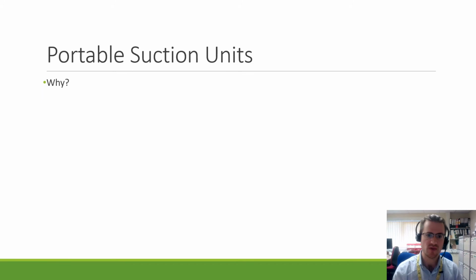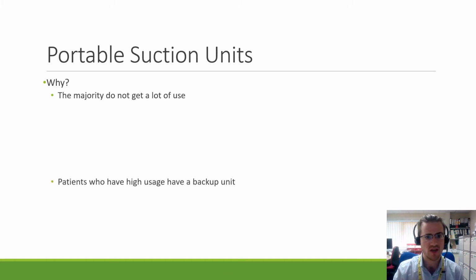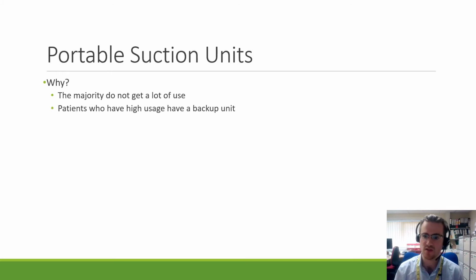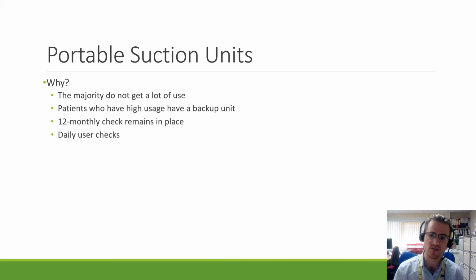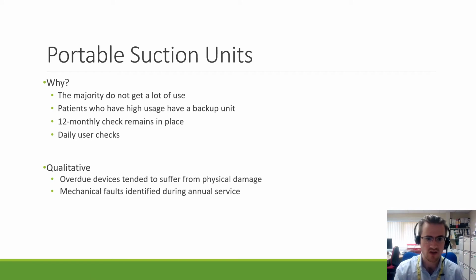For portable suction units, why did we consider them suitable? Well, the majority, especially in hospital, don't get a lot of use. We have wall suction as well as a backup. Patients who have high usage have a backup unit themselves, determined as necessary by the respiratory team. They also undergo 12 monthly checks by our experienced tech teams, and they also undergo a daily user check. So we determined that that would be enough to identify any of the faults. Qualitative data, well, overdue devices tend to have suffered mainly from physical damage, and any of the mechanical faults that we identified were during annual services anyway.